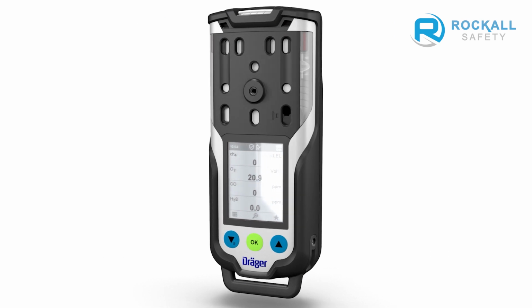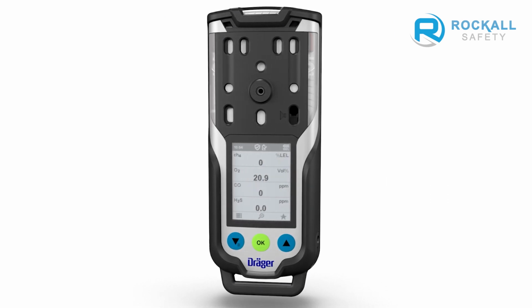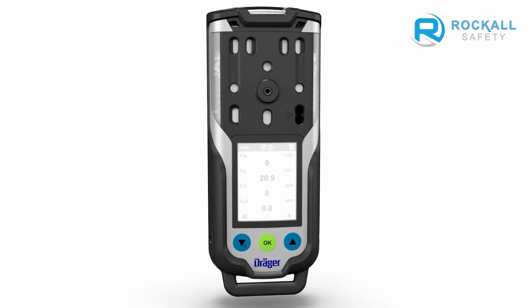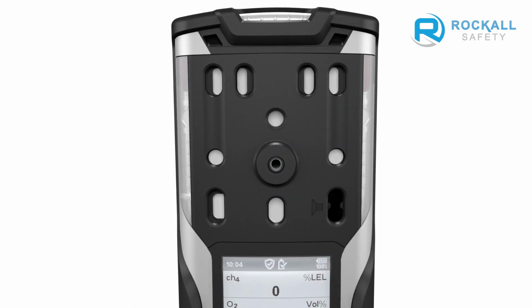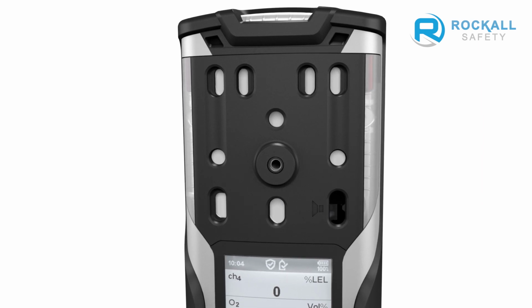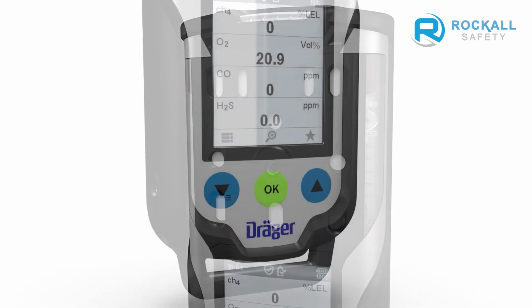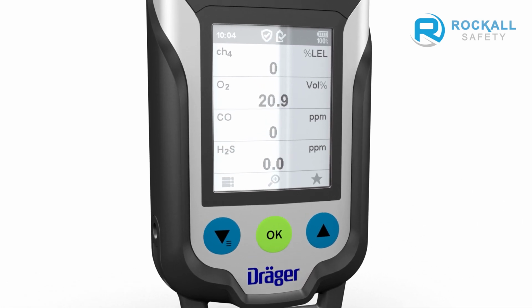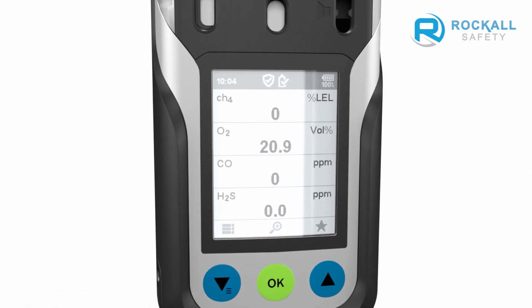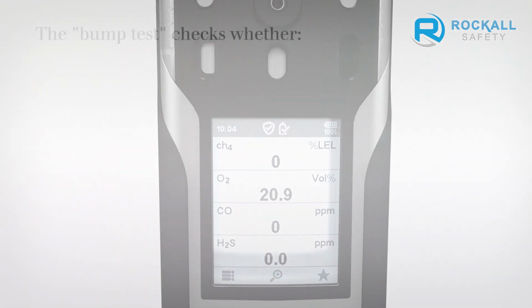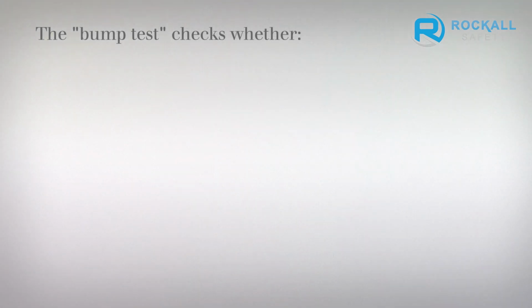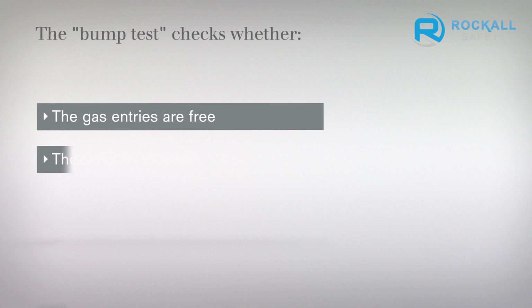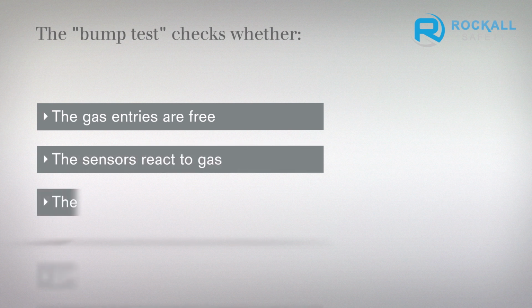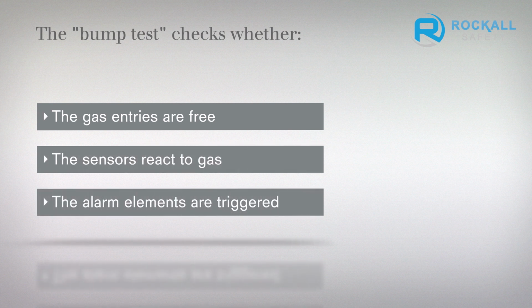Before carrying out safety-relevant measurements, check the function by means of a bump test and inspect all alarm elements. If national regulations exist, the bump test must be performed in accordance with these regulations. A malfunction may lead to incorrect measurement results, which in turn can cause serious damage to health. The bump test checks whether the gas entries are free, the sensors react to gas, and the alarm elements are triggered. If the device fails the test, perform a calibration.